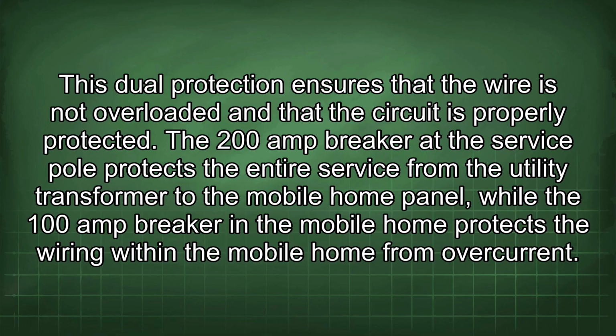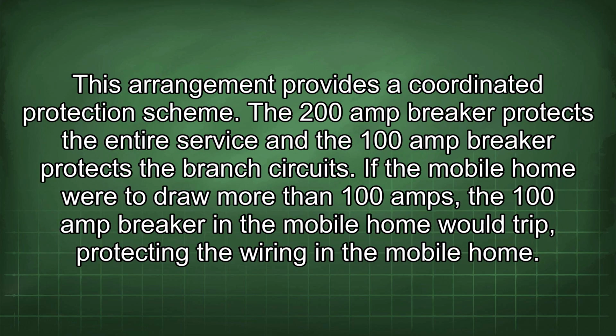The 200 amp breaker, the service pole, protects the entire service from the utility transformer to the mobile home panel, while the 100 amp breaker in the mobile home protects the wiring within the mobile home from overcurrent. This arrangement provides a coordinated protection scheme. The 200 amp breaker protects the entire service and the 100 amp breaker protects the branch circuit. If the mobile home were to draw more than 100 amps, the 100 amp breaker in the mobile home would trip, protecting the wiring in the mobile home.